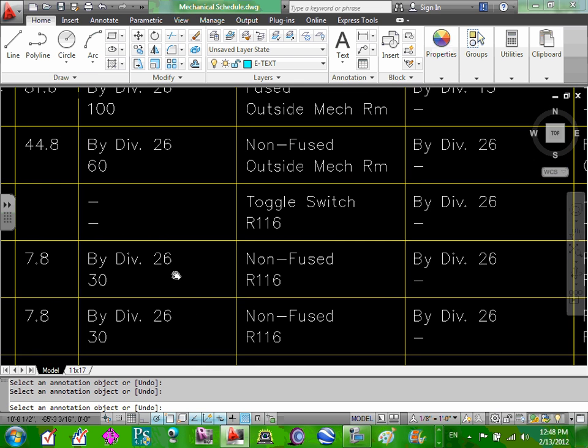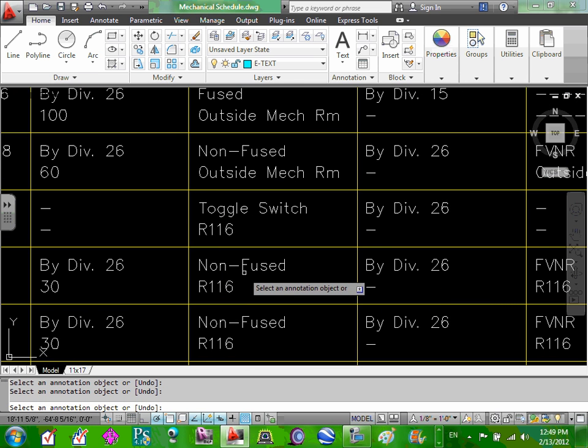And then you come over here. Did they say anything about fuse? No, so it's going to be non-fused. They need a disconnect, but non-fused. Where is it going to be located? Room 116, because they say so, right? And division 16 says located in the electrical mechanical room. So if the pump is located in the room, 99% of the time the disconnect will be right next to it. Make sure, right? So that makes sense? All right, so that's the location.